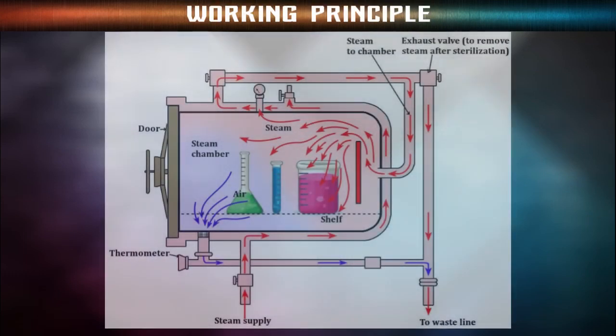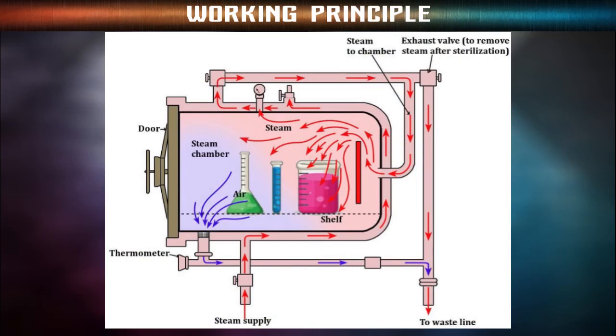Coming to the working principle of this autoclave, the autoclave works on the principle of moist heat sterilization, where steam under pressure is used to sterilize the material present inside a chamber. The high pressure increases the boiling point of water and thus helps achieve a higher temperature for sterilization. Water usually boils at 100 degrees Celsius under normal atmospheric pressure. However, the boiling point of water increases if the pressure is increased.